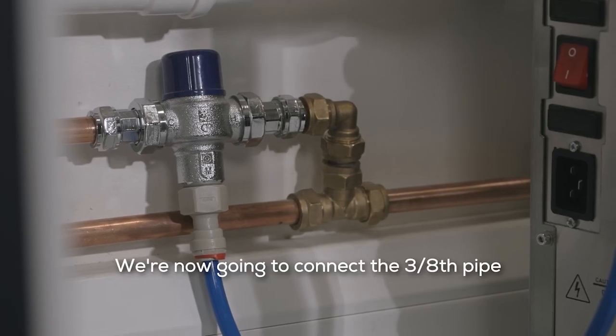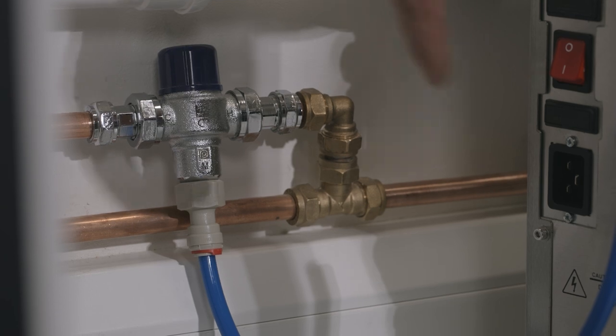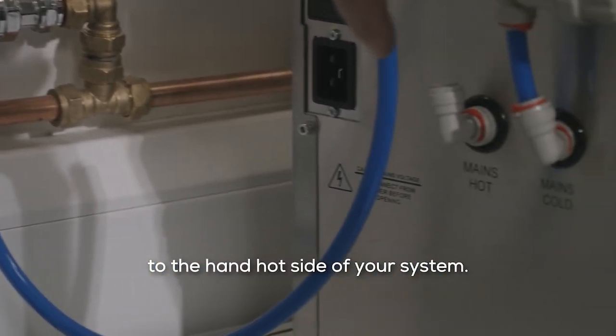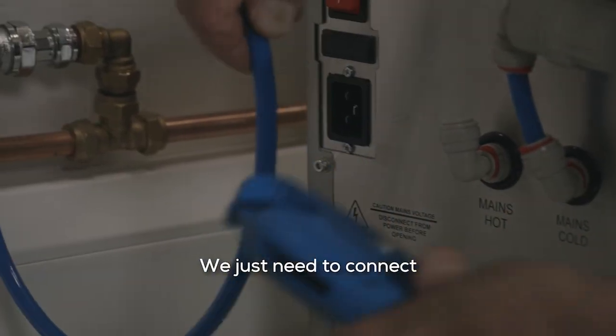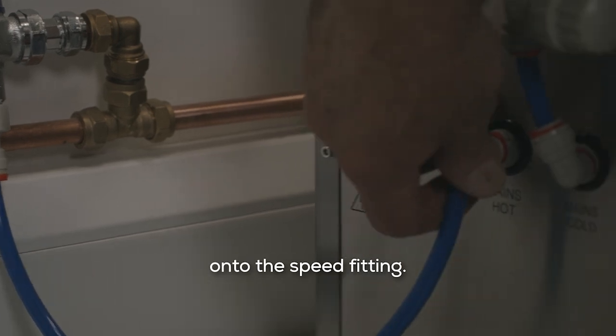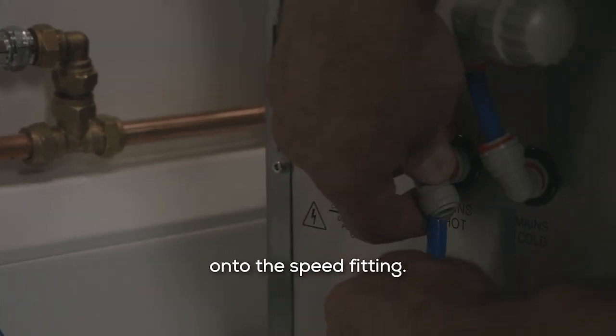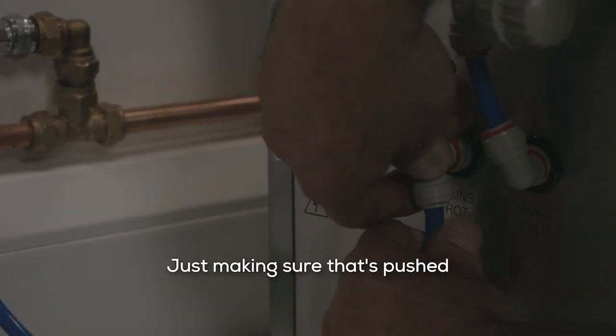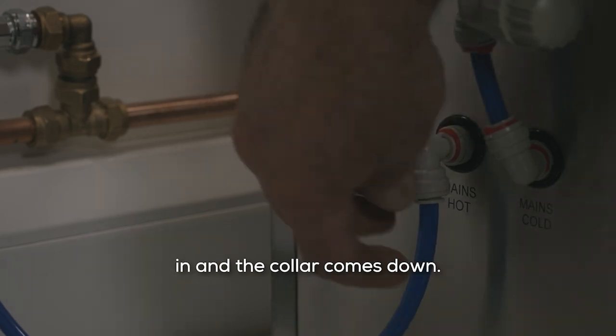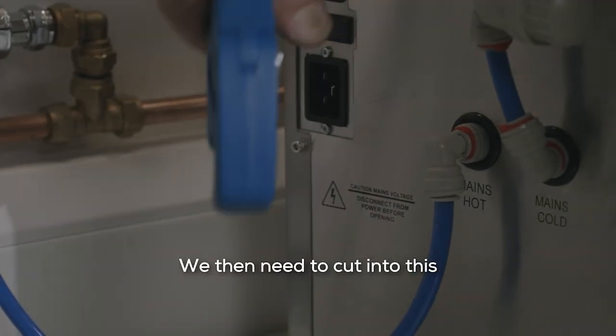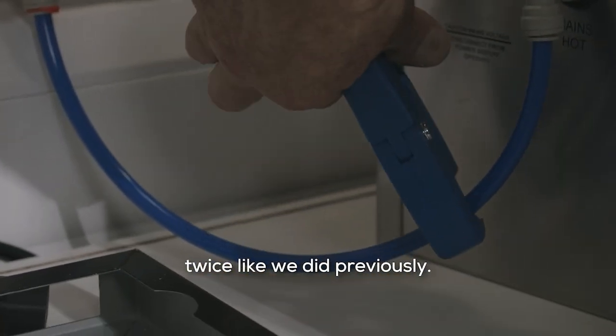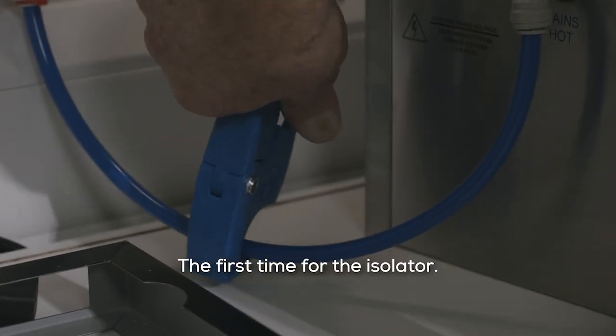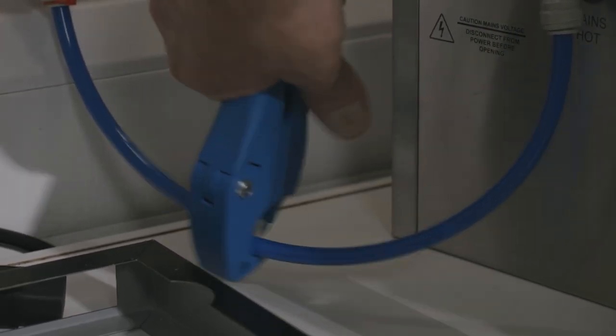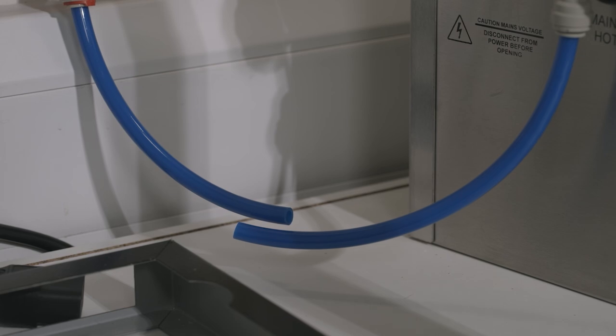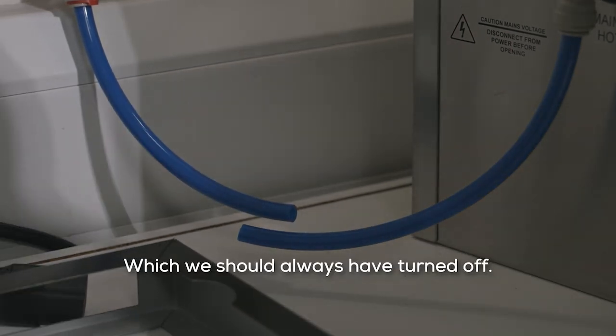We're now going to connect the 3/8 pipe from the thermomixing valve to the mains hot side of your system. We just need to connect onto the speed fitting, just making sure that's pushed in and the collar comes down. We then need to cut into this twice like we did previously. The first time for the isolator, which we should always have turned off.